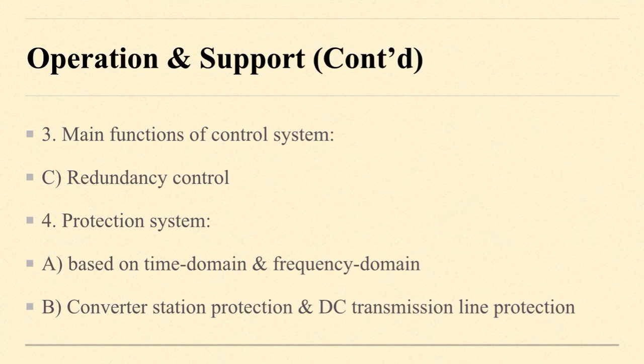Here is protection system. First, protection based on time domain information and protection based on frequency domain information. Protection based on time domain information uses the sampling value for calculation, in which the overcurrent, low voltage, and other protection principles can quickly detect the occurrence of the fault, but it is actually difficult to consider selectivity at the same time. That is, the setting value is difficult to set.